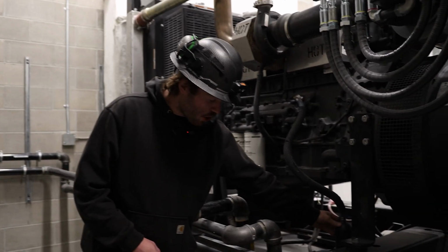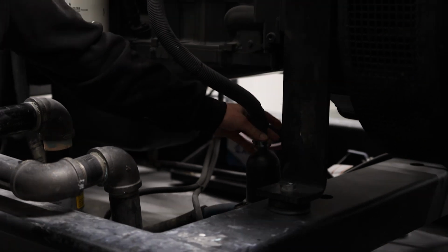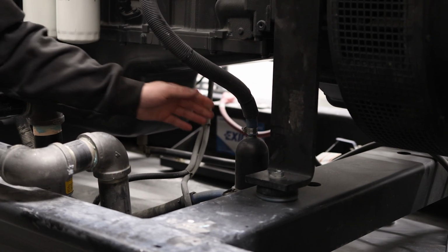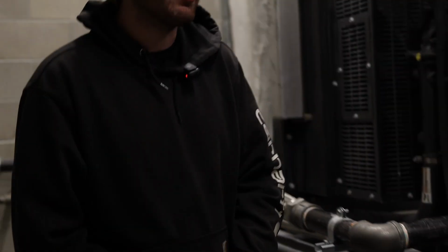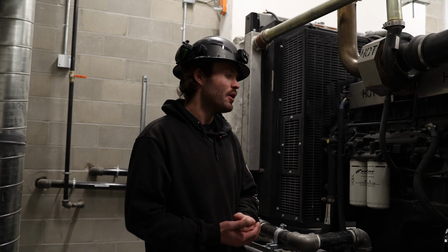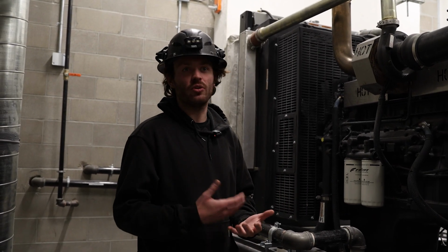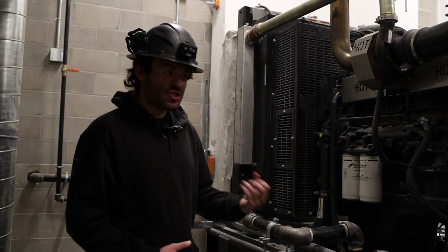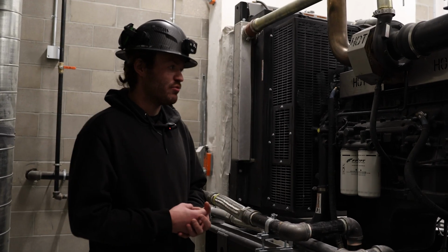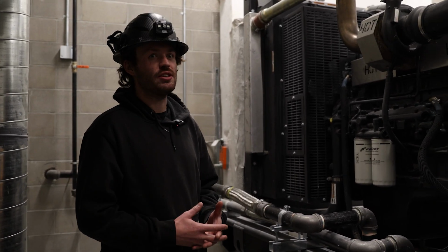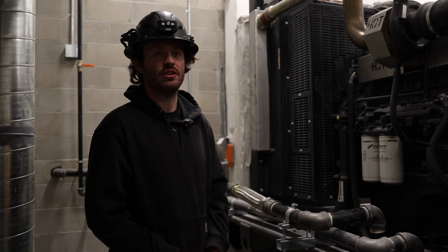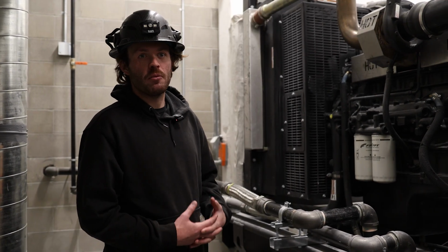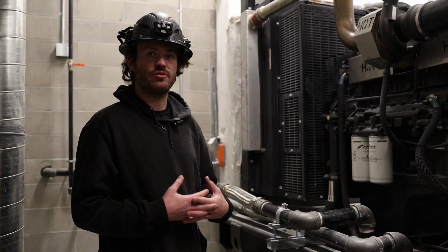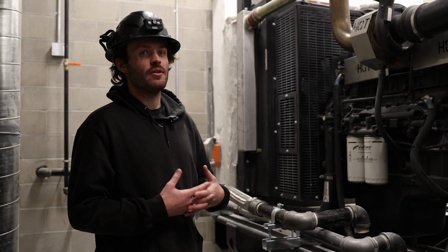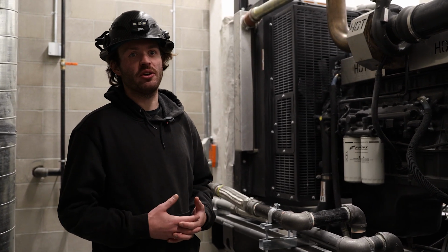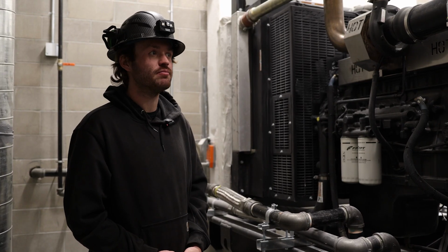Down on the bottom is our block heater for the unit. This will be on year-round. It's got its own thermostat in it, so it'll shut off when the temperature gets to the point where it's too warm, but it'll come back on when it's cool enough. It circulates through just radiation, and it'll end up keeping the whole engine at about 110 to 115 degrees Fahrenheit year-round. We want to keep it warm even in the summer months just for quickness of starting. The whole unit itself has to start and be carrying your building in sub 10 seconds, which it does.